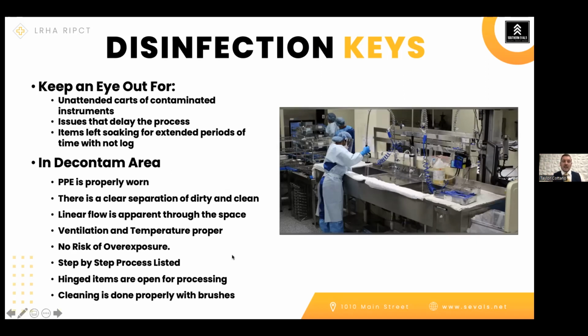In the decontam area, when you're processing, make sure that if you pack items, the hinge or ratchet that shuts is kept open. This is another easy finding, because if those things are closed they can't be disinfected properly. You want to make sure they're hinged open so they can be completely decontaminated or sterilized.